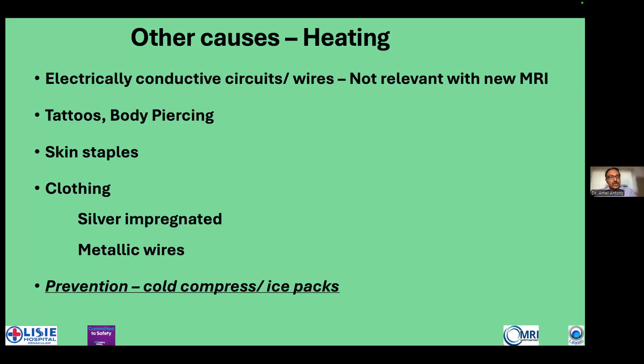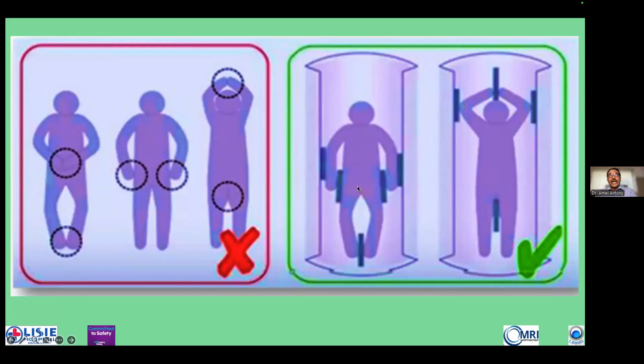So that is just a pictorial representation of how patients should be positioned within the gantry. You can see here that there is adequate padding between not only the gantry and the patient's body, but between the different body parts, so that body parts don't come into contact with each other. And this can induce electrical current there and cause heating. So that's a proper way of positioning there.